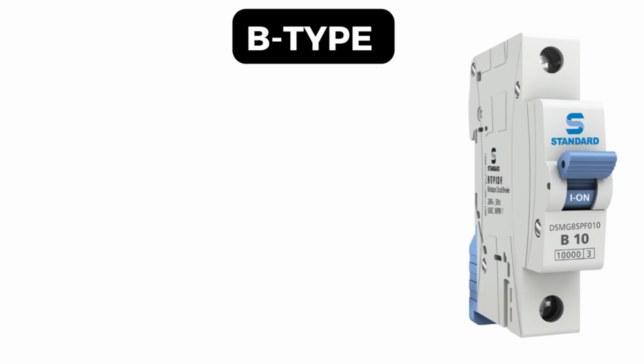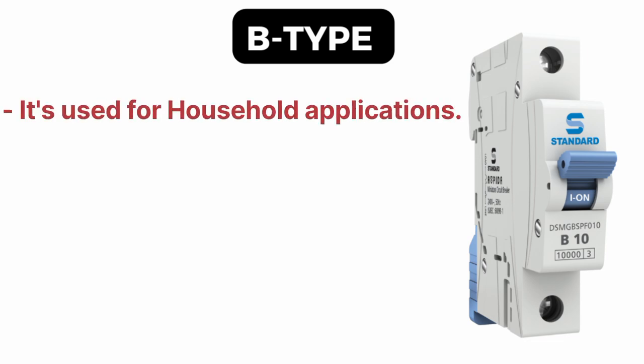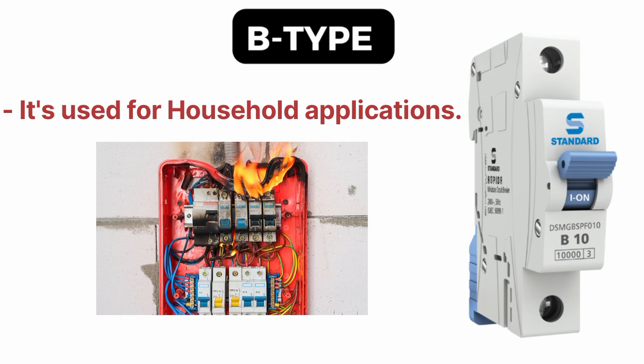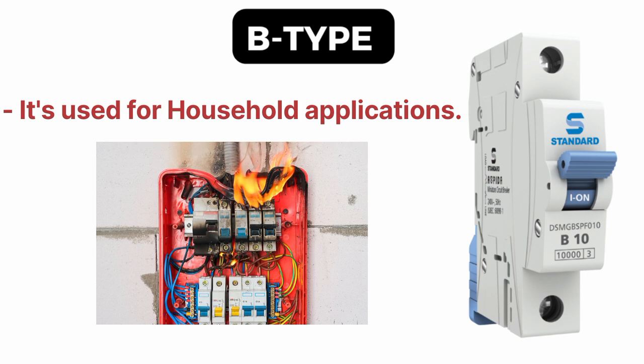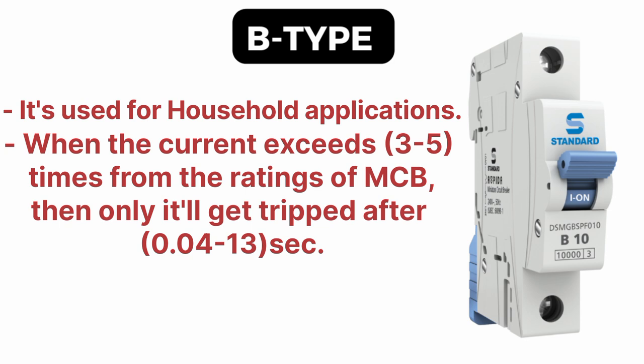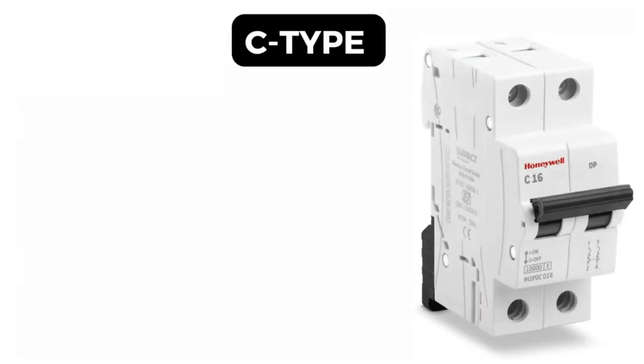Type B MCB is generally used for household applications. If you want to protect the electrical system from overload in our homes, we should use the Type B MCB. It gets tripped when the current exceeds 3 to 5 times the rating of the MCB, and it will trip after 0.04 to 13 seconds from the overload.